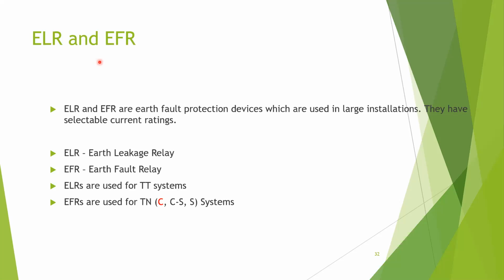From the knowledge you gained from previous studies, you know TT systems have a higher earth loop impedance, therefore we have a lower earth fault current. In TN systems, we have a lower earth loop impedance and a higher earth fault current. So for residual current devices used for these two systems, for TT we use ELR. ELR means earth leakage relays. These are the residual current protection devices used in TT systems in large installations. The term leakage stands for small currents.